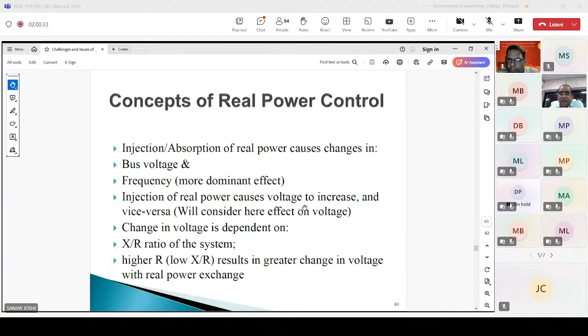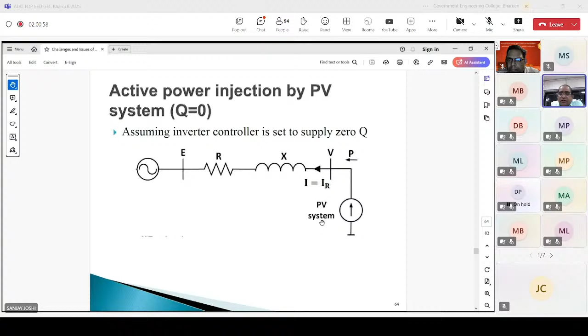The pool generation is 1,000 megawatt, 3,000 megawatt, 2,500 megawatt and so on. So the problem we have discussed becomes predominant here. This reactance is weak, it is high, and a huge amount of power is being pulled. So the voltage becomes very sensitive to changes in active power injection and reactive power injection in this remote area of Rajasthan because of the low fault level. This should have been higher; the fault level should have been higher.